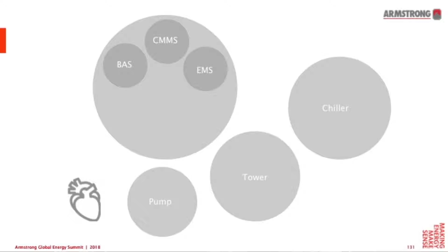The pump, because it has built-in DE technology, starts saving energy from day one. That retrofit is guaranteed cash flow positive from day one. But what a DE pump also does, as we mentioned earlier, is it doesn't just look at itself, it looks at the entire system. So once you have the DE pump in the system, it actually brings savings on the condenser side as well as the chiller side. The total savings with that move is approximately 10%, and this is totally cash flow positive from day one.